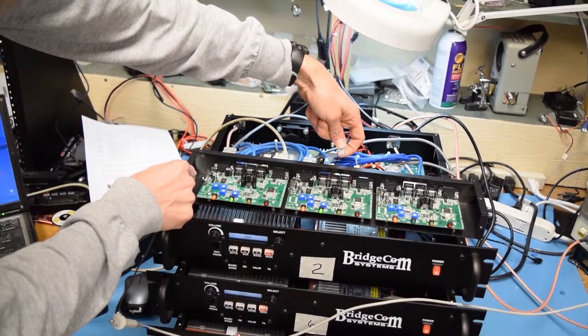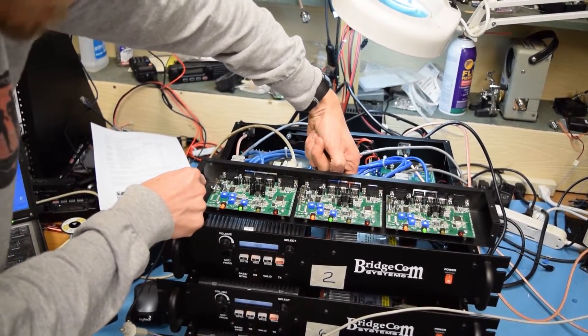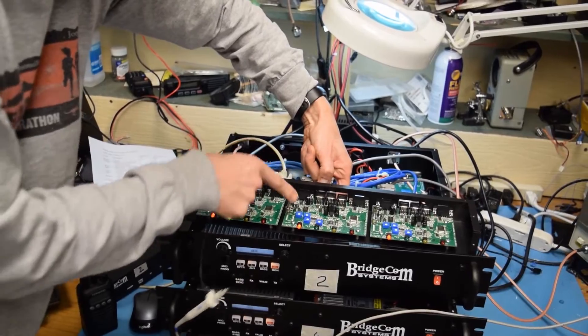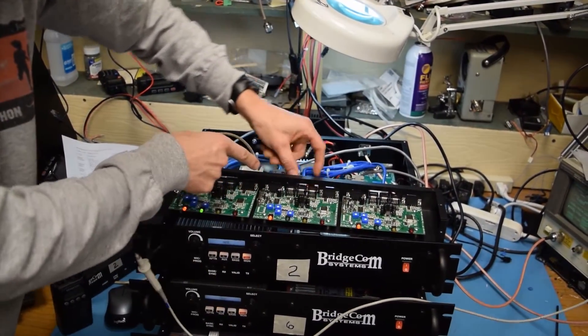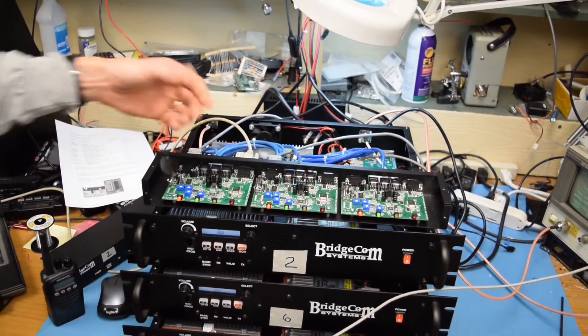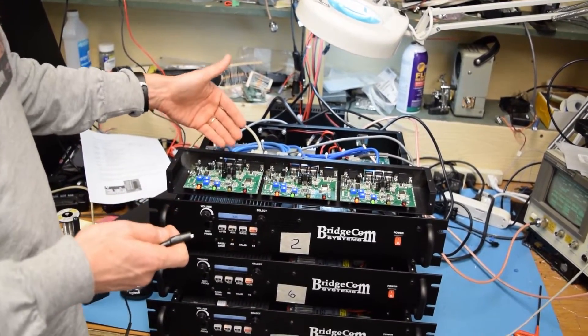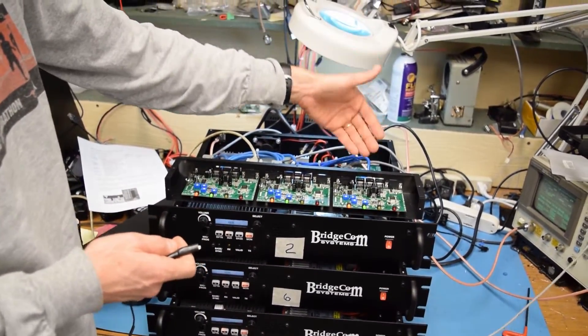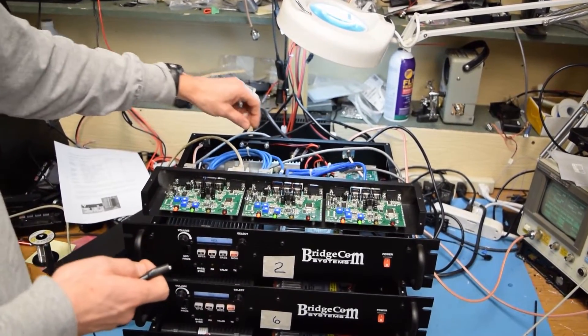You'll notice that when I take this one out, it goes out, and if I pull this one out, both of them should go, because they're in line there, so it's a series connection. So that's very important. You have to have these jumpers installed on the ends of the bus, no matter what the cable lengths are.